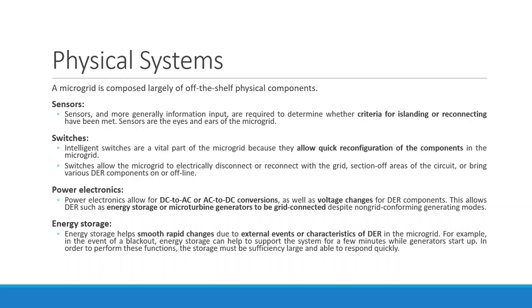Okay. The other thing a microgrid consists of is the power electronics. We know that the converter is important because it allows conversion of power from DC to AC and AC to DC. This conversion is required, as well as voltage changes, for the distributed energy resources components, that is, the DER components. So the power electronics converter allows distributed energy resources such as energy storage or micro turbine generators to be grid connected. Basically, any distributed generation cannot be directly connected to the main grid. At least the voltage and frequency criteria should be met. The frequency should be the same.